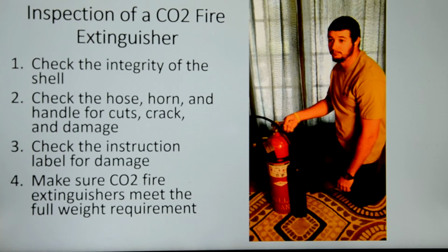Inspection of a CO2 fire extinguisher. Check the integrity of the shell. Check the hose, horn, and handle for cuts, cracks, or damage. Check the instruction label for damage. Make sure it's not ripped off or any of the instructions are missing.